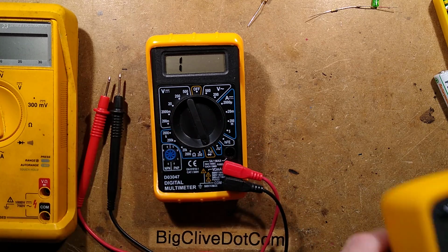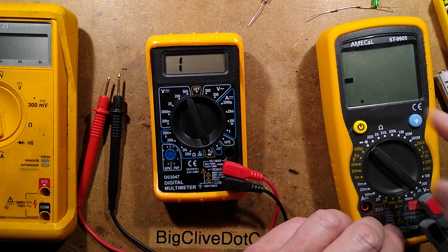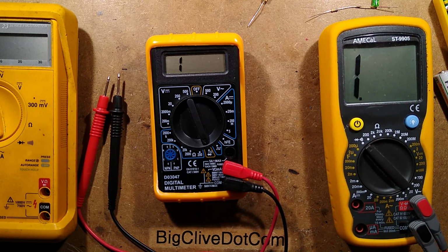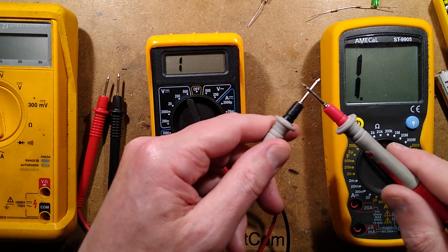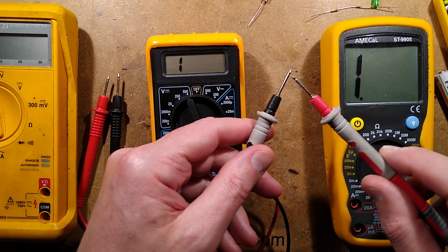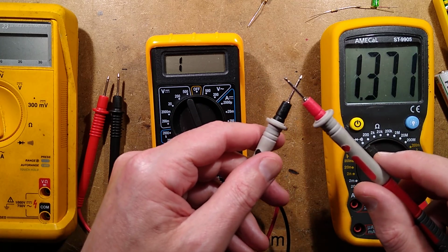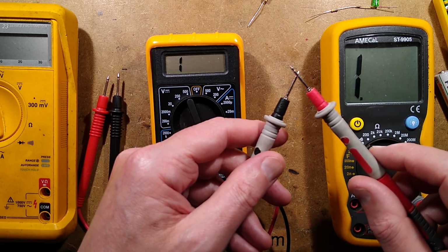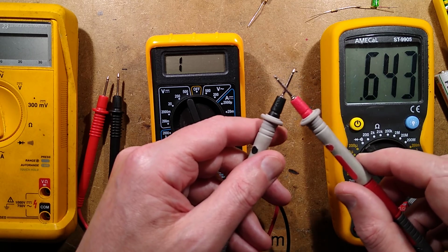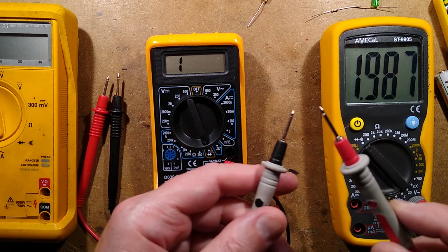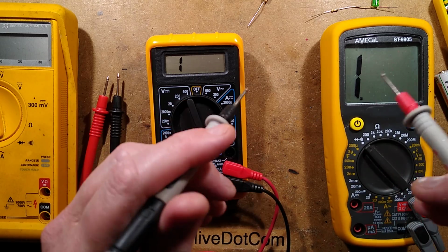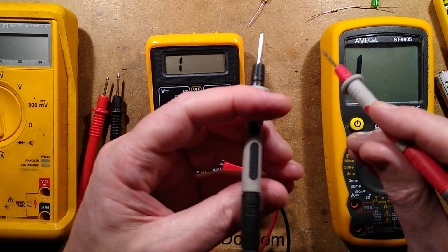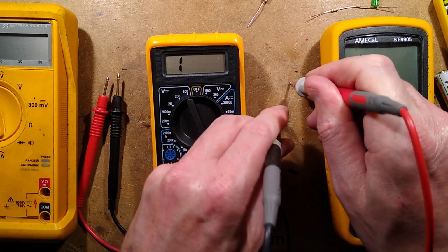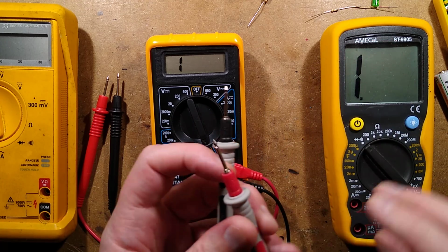My preferred meter here, with its big display, is more instantaneous and it's scratchy. This is what Dave calls a scratchy tester, because it beeps instantly, and if there's any bad connection, it hisses and crackles and scratches. I prefer that because it's faster, and also, even if you get a good connection, if it's still crackling and buzzing, it means that there's actually a bad connection.